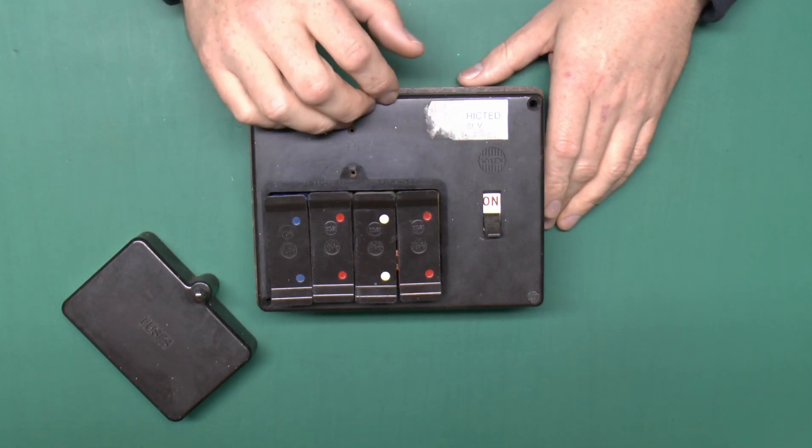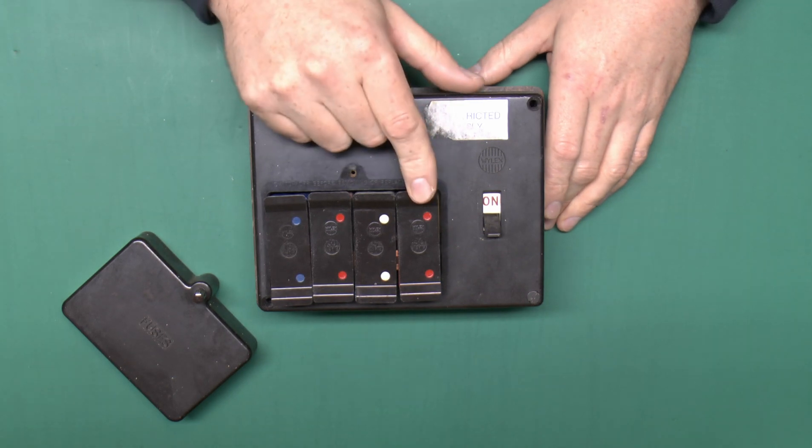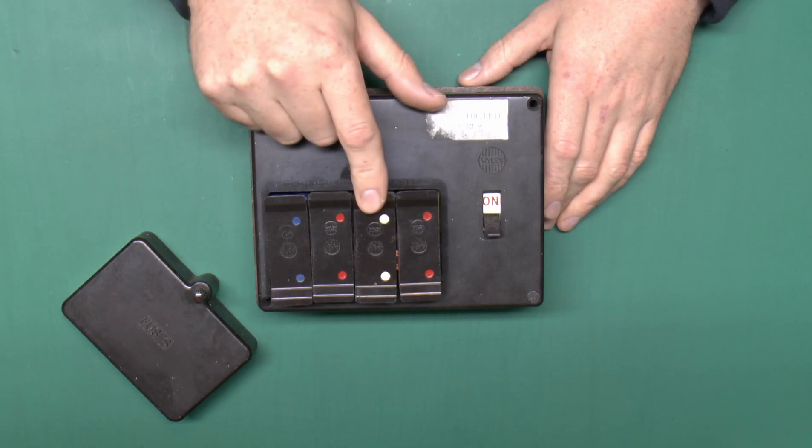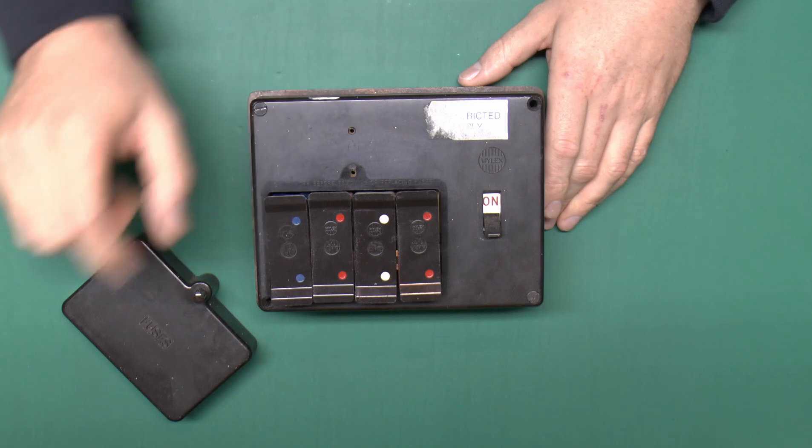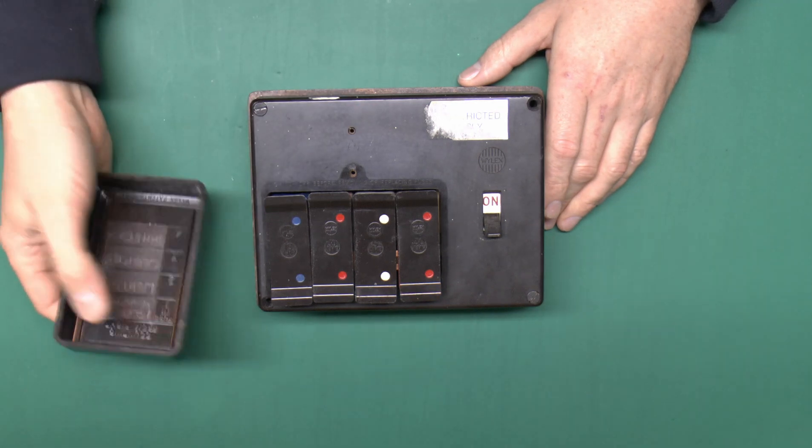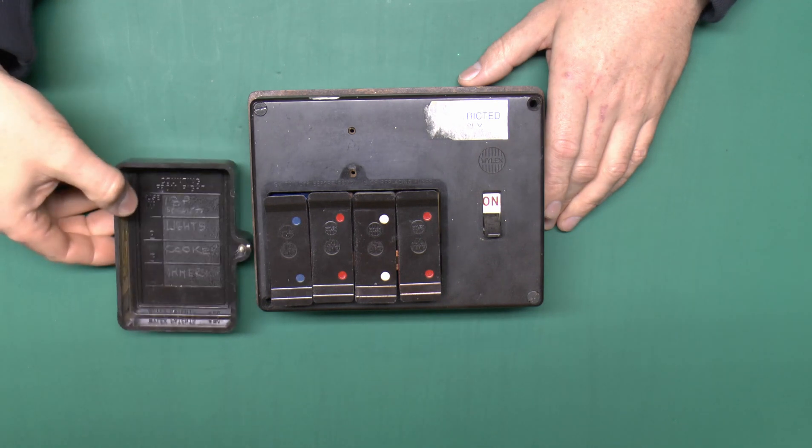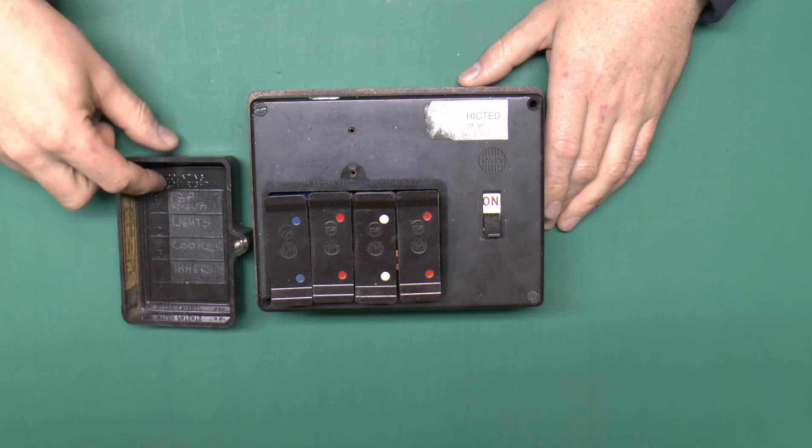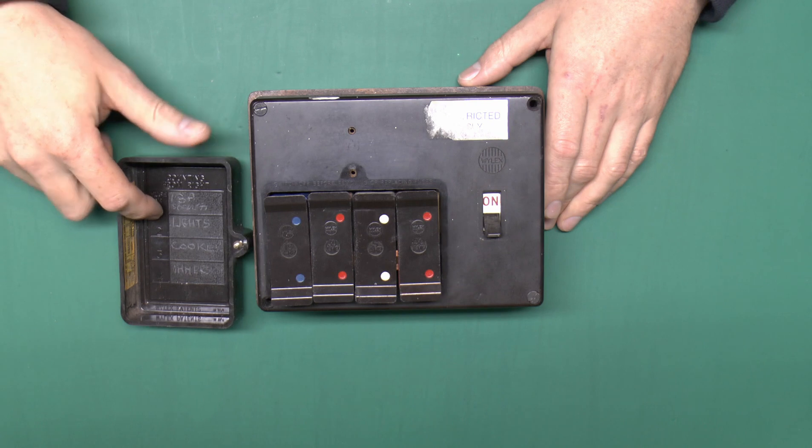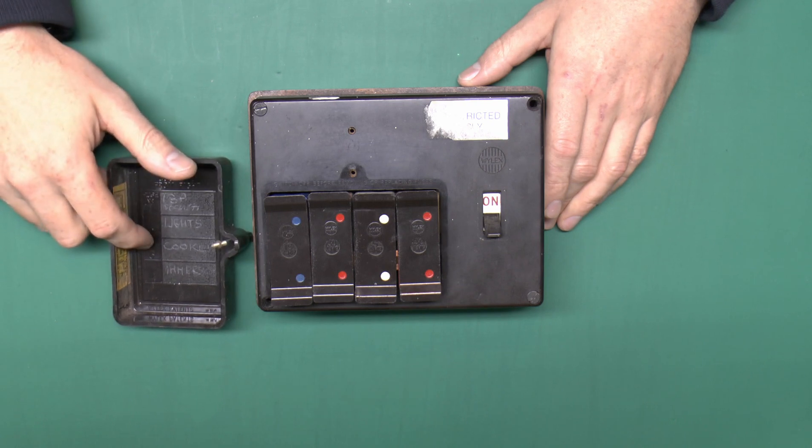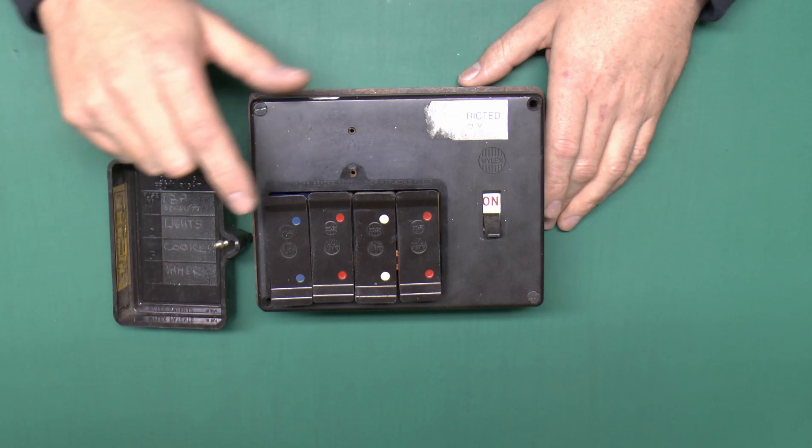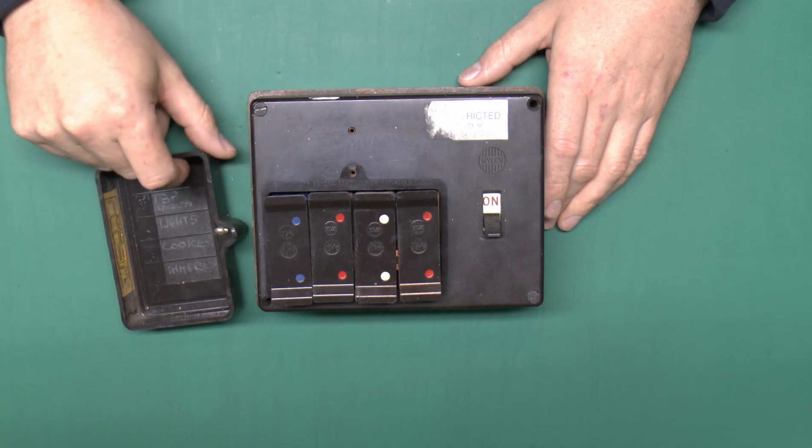This particular one has the usual set of four fuses in there, 30 amps for the red and 5 amps for the white, 15 amps for the blue one. The cover here astoundingly does actually have the things marked inside. So we've got sockets, lights, that's the 5 amp one, cooker 30 and immersion or immersion heater which would be the 15 amp blue one at the end.